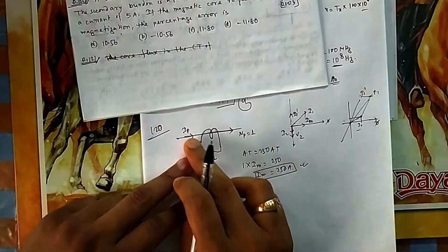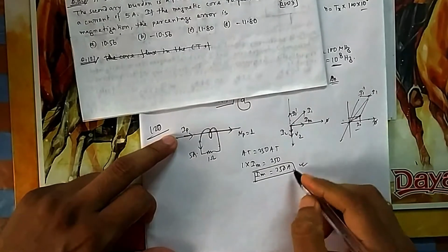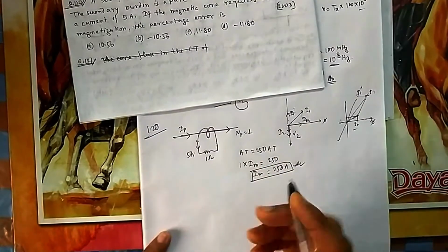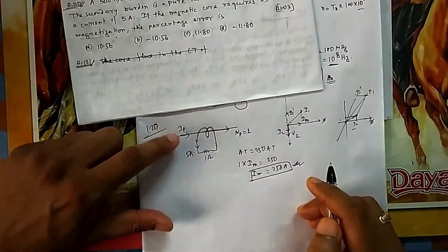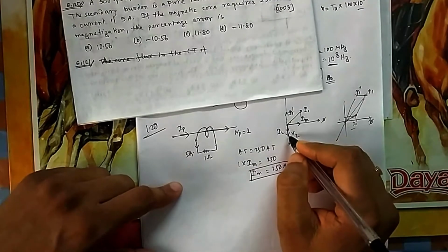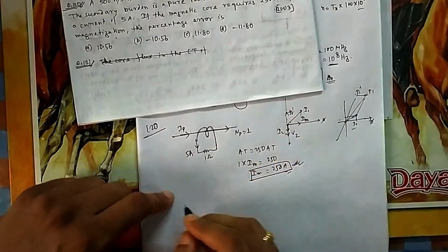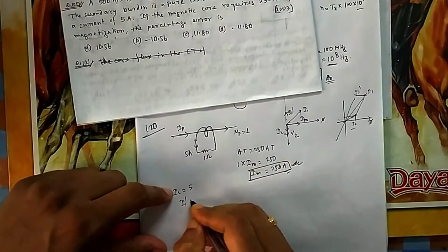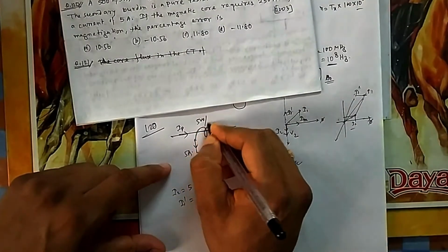So this is your IM, and I1 dash is what is reflected here as I2. Whatever current you give the primary, some portion will go for magnetization, and whatever is left will be reflected in the secondary. That is the idea. That's why the error comes. Whatever input is on the primary side is not properly reflected in the secondary, because some portion has gone to this. So now I am calculating I2, which is I1 dash. I2 is given as 5 ampere. So the corresponding I1 dash will be how much, because the ratio is 500 to 5.